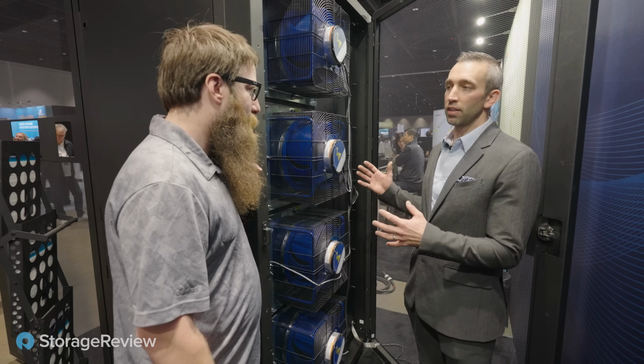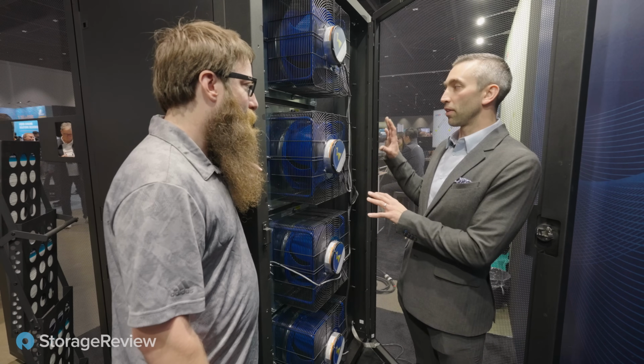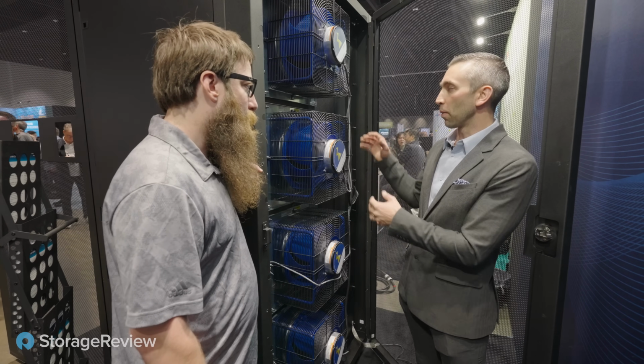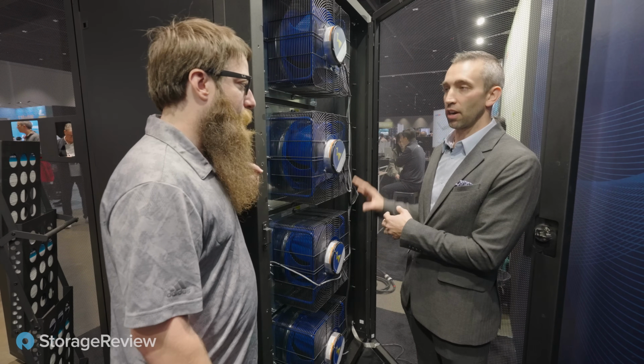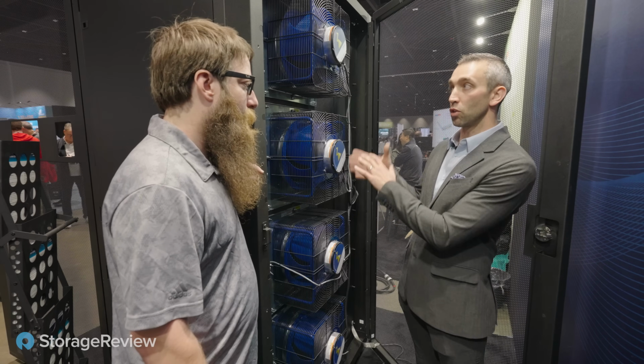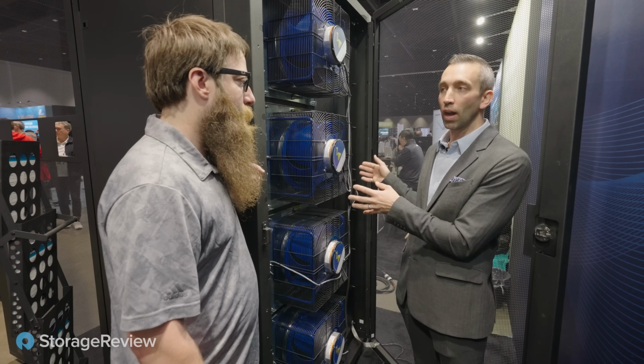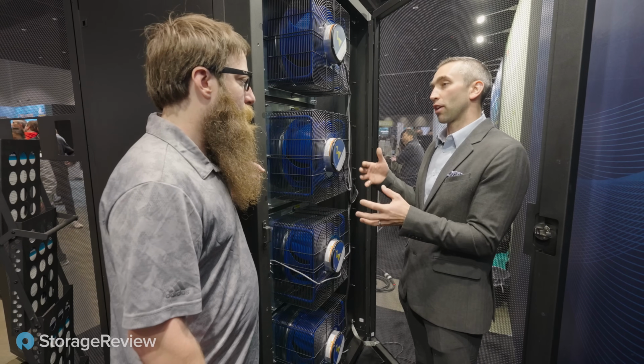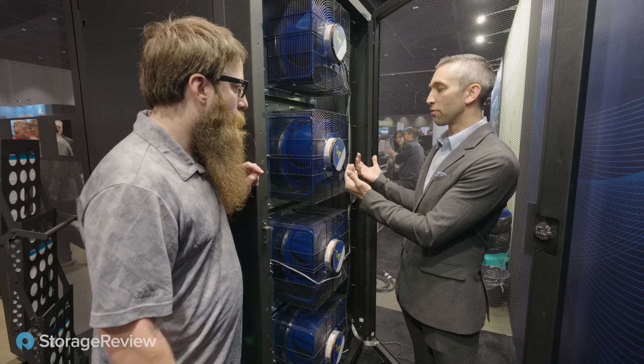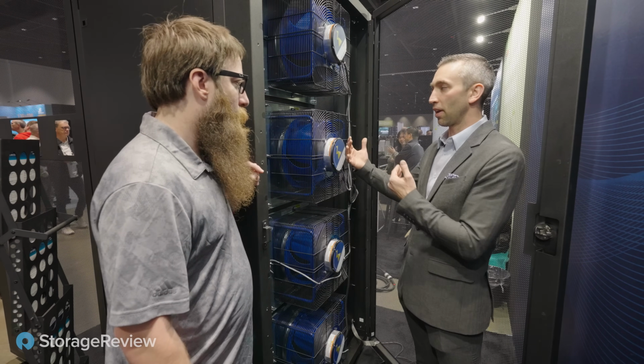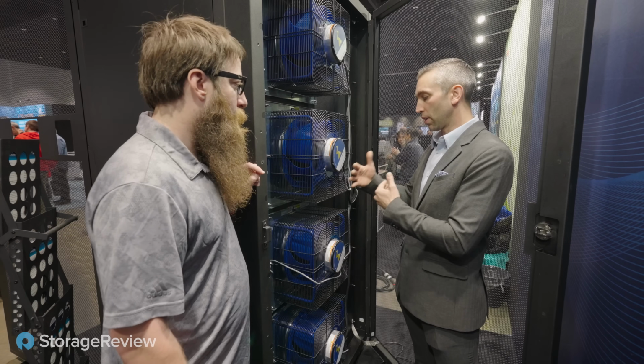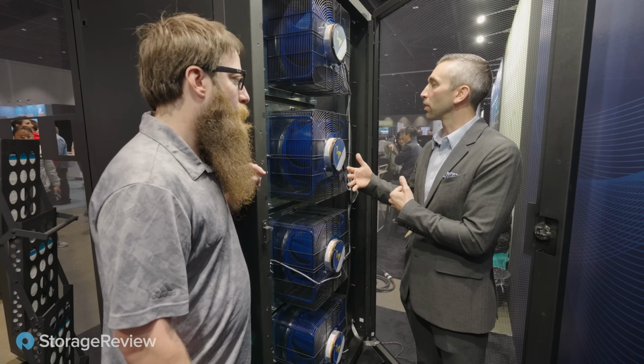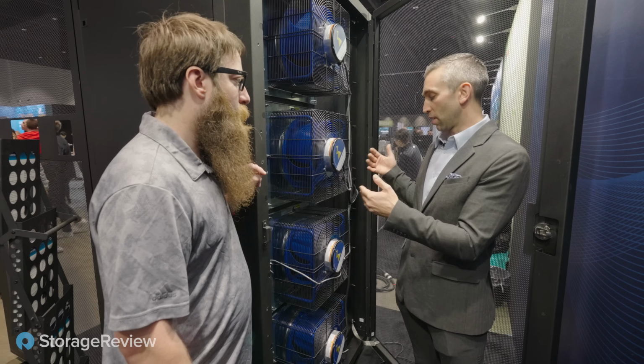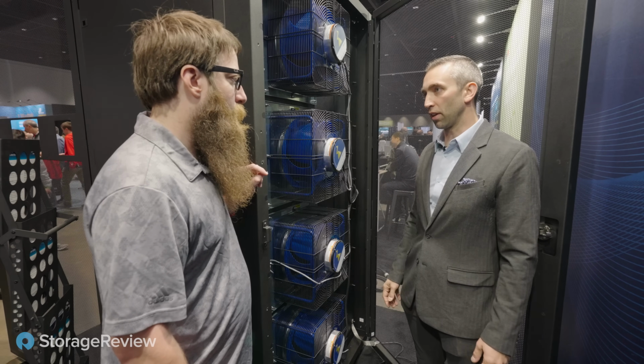We have 2 variants of this product, the only difference is on the backside of the CDU. In this case we have 4 fans - this is our AHX180, rated for 180 kilowatts. We also have the AHX240 which has 8 fans, and the main difference is the depth. For this one we limited its depth based on some customer requirements, and we have a deeper version for the 8 fan unit that does 240 kilowatts.